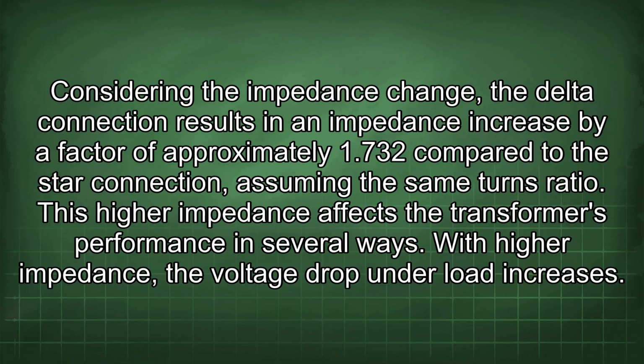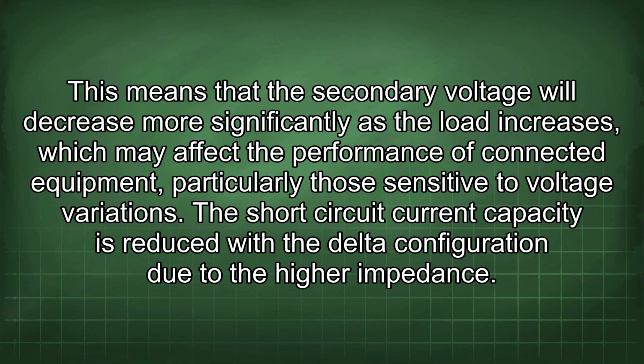Considering the impedance change, the delta connection results in an impedance increase by a factor of approximately 1.732 compared to the star connection, assuming the same turns ratio. This higher impedance affects the transformer's performance in several ways. With higher impedance, the voltage drop under load increases. This means that the secondary voltage will decrease more significantly as the load increases, which may affect the performance of connected equipment, particularly those sensitive to voltage variations.